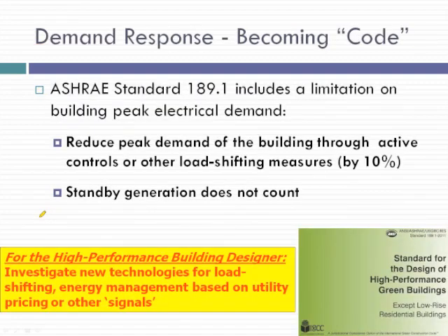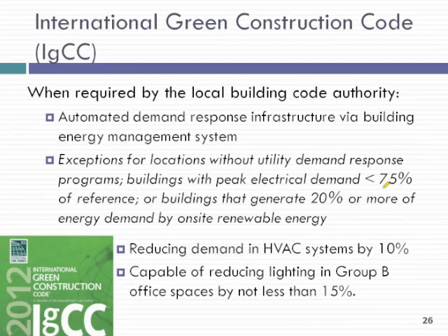10% is a similar number that the ASHRAE standard 189.1 for high performance green buildings has come about, stated more simply in the sense that you have some system in place where you can reduce the peak demand of a building through active controls, load shedding, whatever, again by that same 10% scenario. 10% seemed like a magic number to people creating those standards. I'm on the standard 189 project committee, so there wasn't anything magic about that—it just seemed achievable, and some studies have shown it was achievable.